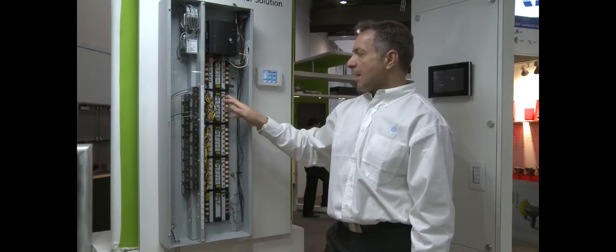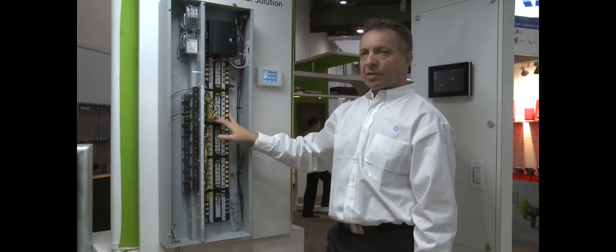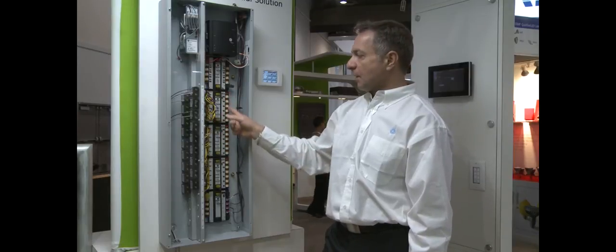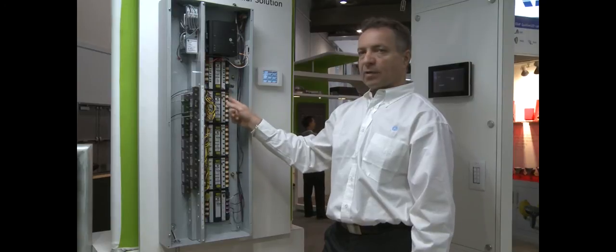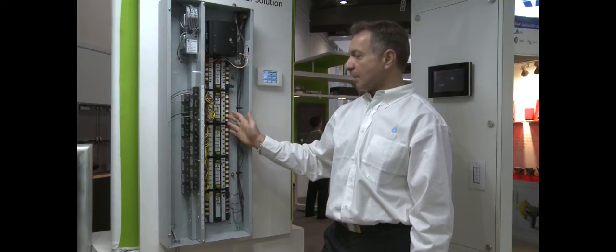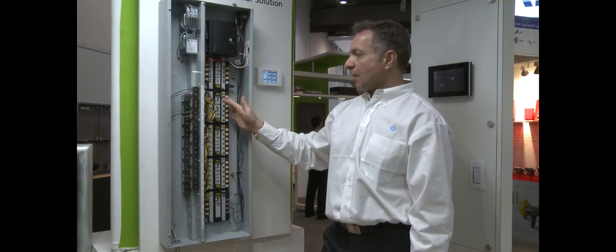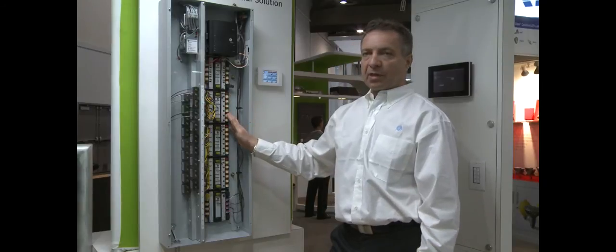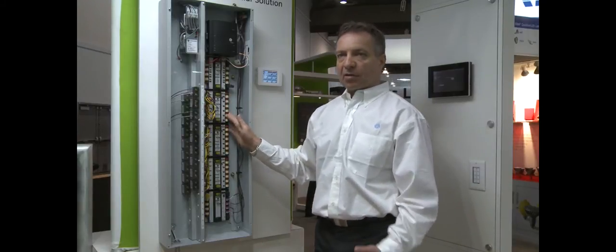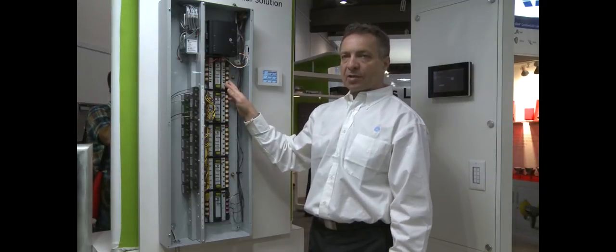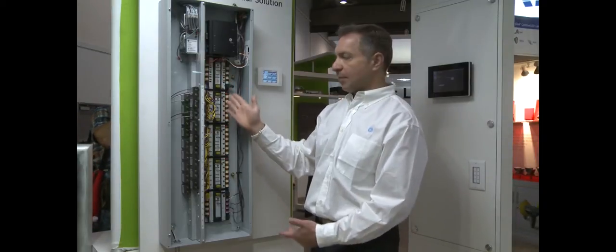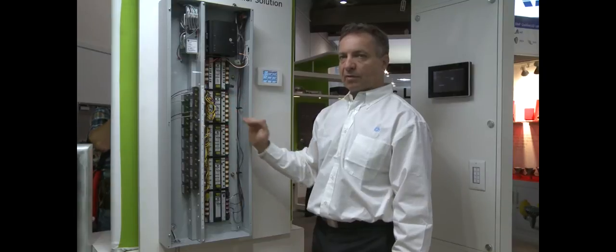There are two versions of the relay modules. Some of them have switch inputs. These ones are non-programmable. They are actually controlling one-to-one. So switch one controls relay number one. And we have an option without switch inputs. So if not requiring that application, they are controlling larger groups of relays. The group modules will handle the controls. So then we can save some money and offer a version without those terminals.